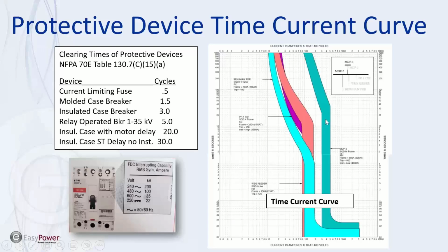So this photo to the left shows time current curves. These will represent different breakers. So this may be a main breaker on the right, and then it may be the main distribution panel, then it may be the main breaker to a 480 volt panel, then a breaker feeding a motor, for example. So that will be the first one you want to trip, and so that's okay for up here. So let's break this down a little bit more.